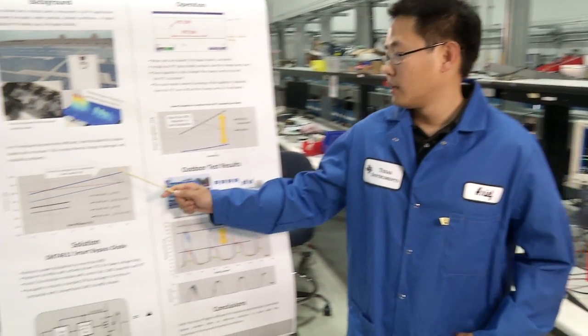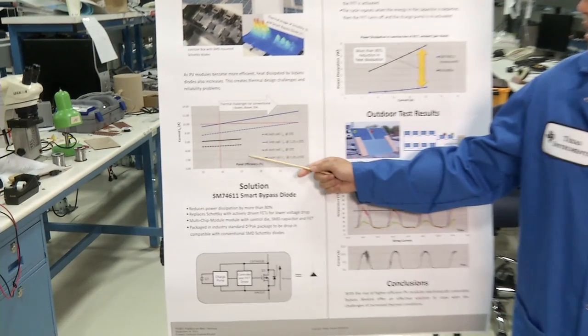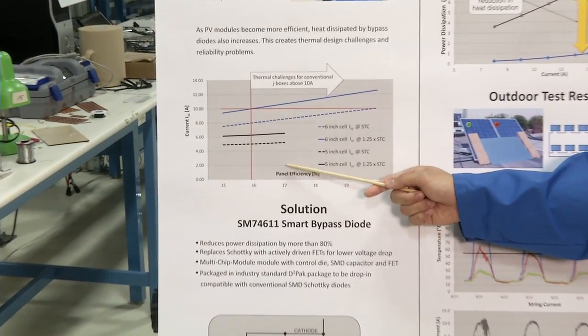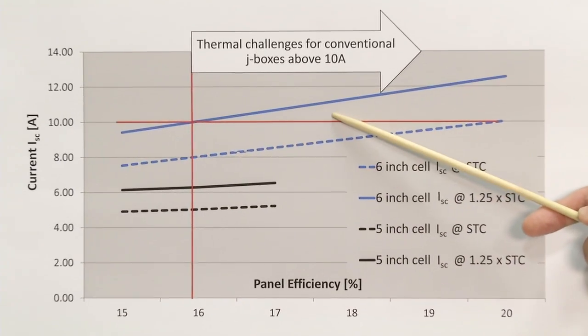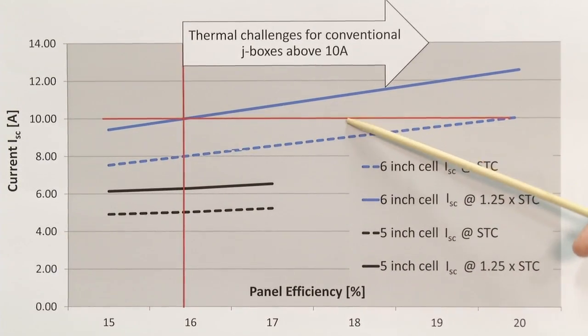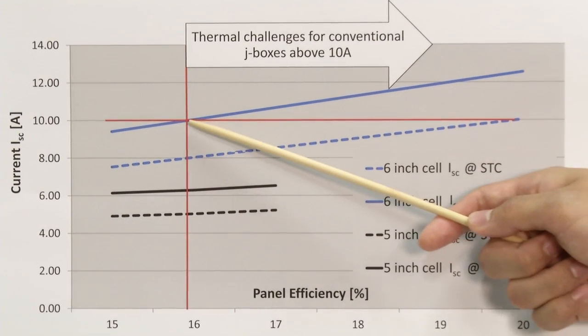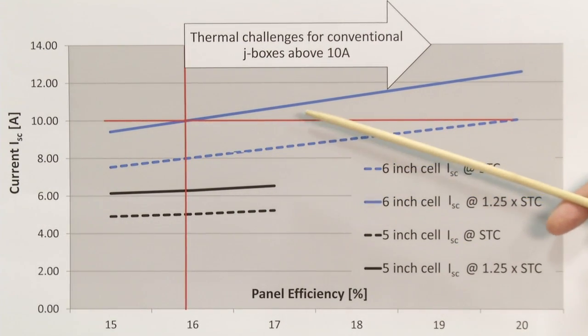A bypass diode is a critical component in PV panels. It is used to mitigate the hot spot that happens on PV panels when the panels are shaded. Normally these bypass diodes are Schottky diodes. As you can see here, when the panel efficiency increases, the current that the panel is able to produce also increases. This will create thermal challenges for Schottky diodes, and at around 10 amps, the power dissipated on the Schottky diodes will be reaching about 4 watts.